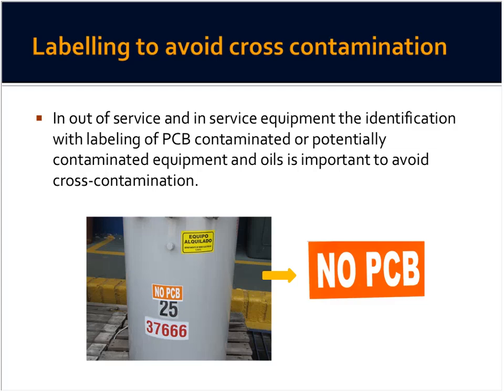Such transformers can continue to be used until 2025. It's very difficult for companies to simply eliminate PCB contaminated transformers if they still have a lifespan left, and there's also the process of repurchasing new transformers to consider. So they may go back into service, but it's important for them to be labeled, and for the information to be tracked in a database or spreadsheet, so you know where the transformer is located, that it has its label, and you can keep track of it when it comes down for maintenance or when it's time to take it out of service.